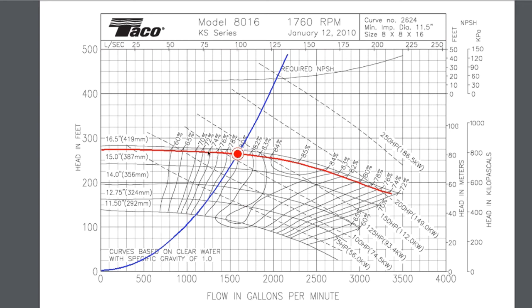Which brings us to power. At that operating point, we're sitting partway between the 125 horsepower dashed line and the 150 horsepower dashed line. Those are lines of differing power levels. The higher the head and the higher the flow — remember power is rho times g times h times Q — the higher the power we need to put in to drive the pump.